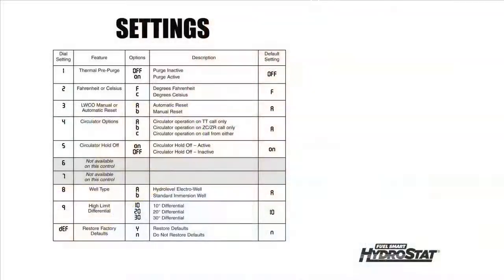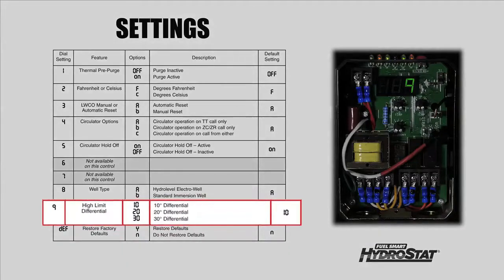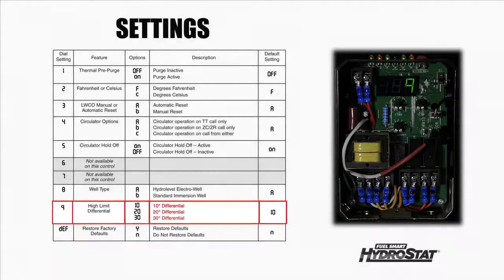Option nine allows you to set a fixed differential of 10, 20 or 30 degrees Fahrenheit off of the high limit setting. This feature can only be used if the economy function is turned off.